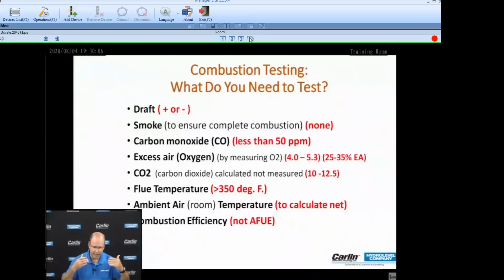And again, the eyes are spinning. Well, what do these numbers mean? Where does the oxygen come from? So now you take them back to that first slide: 21% oxygen in the air. We introduce that in the process of combustion, and whatever's left over in percentage is what was not used up in the combustion process. So if we did not use up the oxygen, then the combustion process wasn't complete. And the more air that's left over, the more oxygen that's left over, the more excess air that we've added. So these two numbers, excess air and oxygen, are totally related.